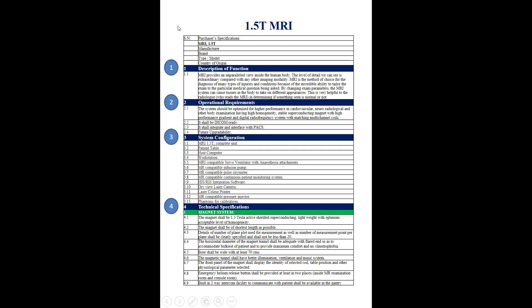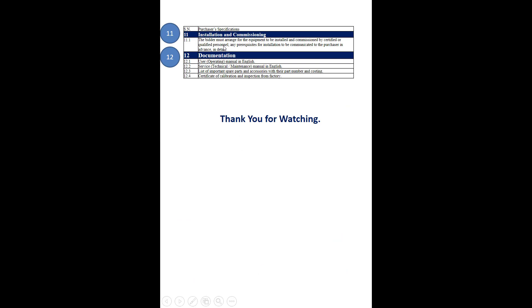The points which should be covered in writing the specification for a 1.5 Tesla MRI include: a description of function, operational requirements, system configuration, technical specifications, accessories, spare parts and consumables, operating environment, standards and safety requirements, user training and service training, warranty, maintenance service during the warranty period, installation and commissioning, and finally documentation.